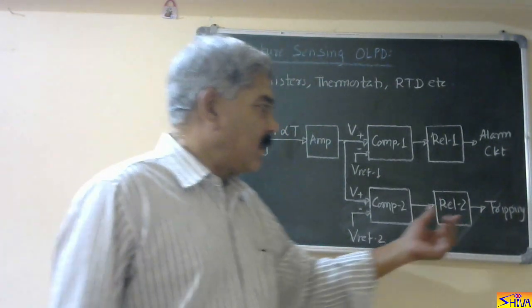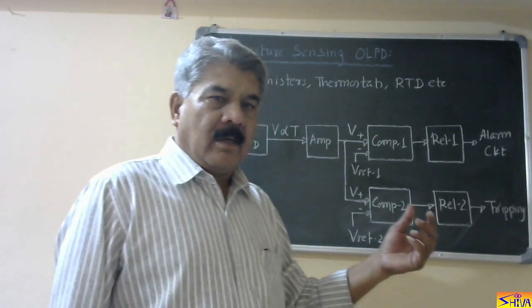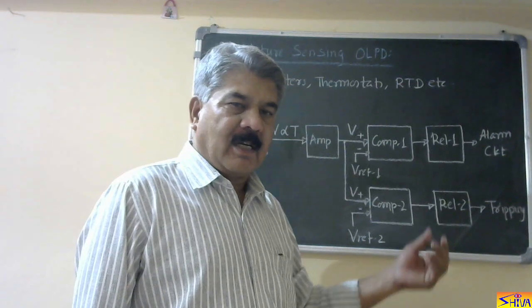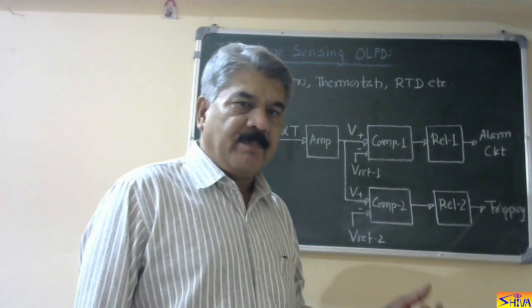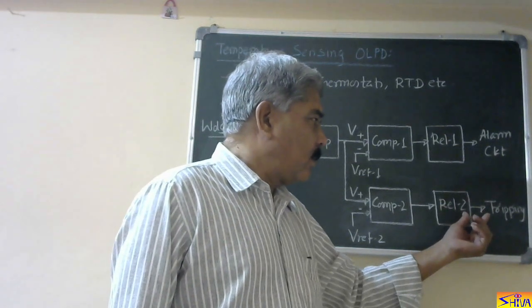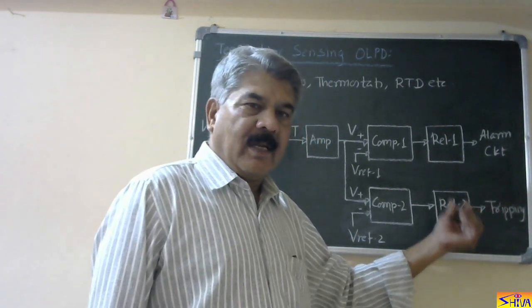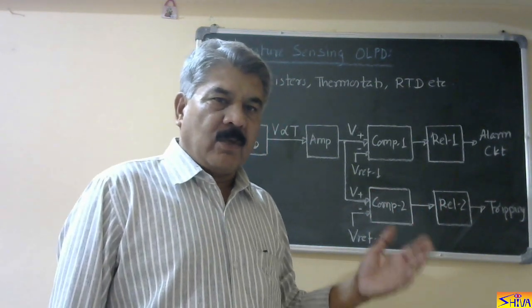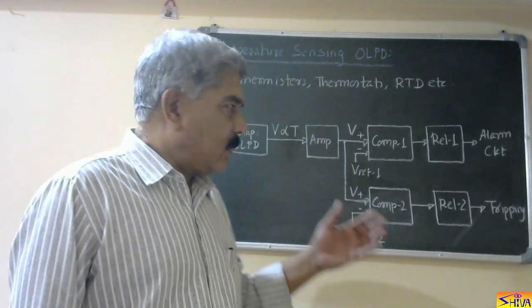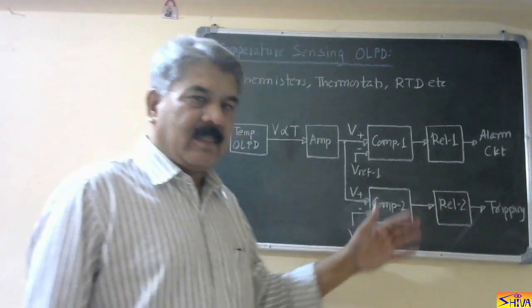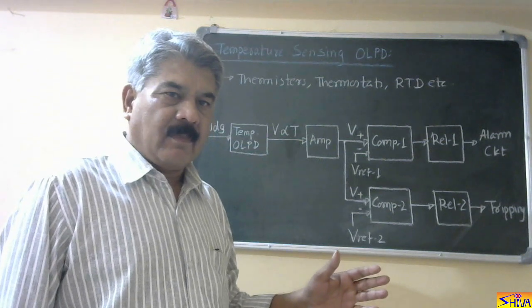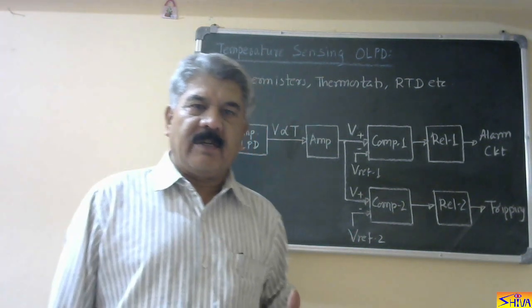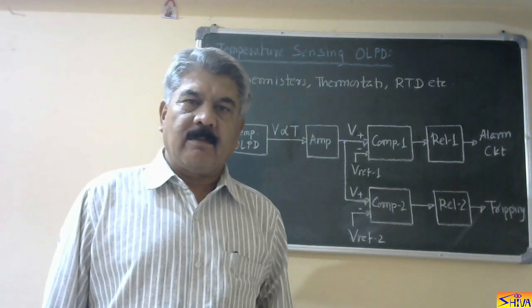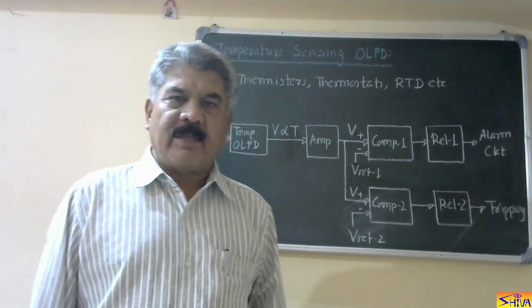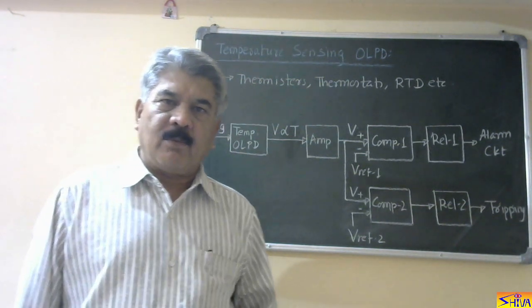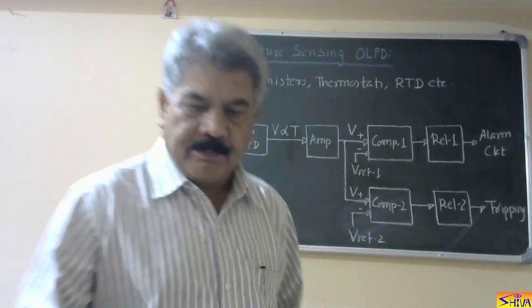from the circuit. This can be connected to the tripping coil circuit of the circuit breaker or the contactor or the MCB or MCCB. So when normally close contact is connected in the tripping circuit, relay 2 operates and its contact opens, so it disconnects the motor from the circuit. So this is how this temperature sensing overload protective device works. So that is all about short circuit protection and overload protection of induction motors by current sensing protective device as well as temperature sensing protective device. Now I will explain protection against some abnormal running conditions.